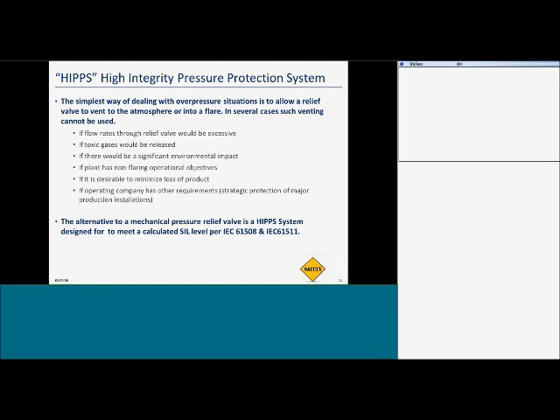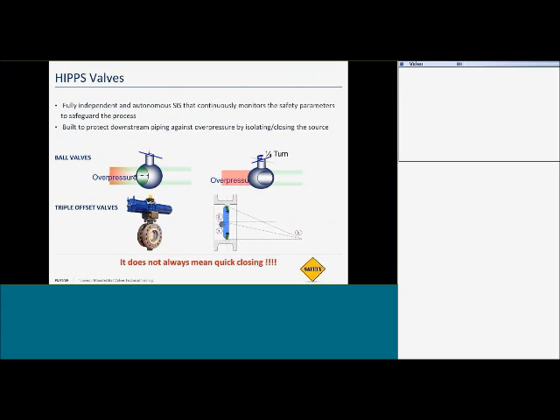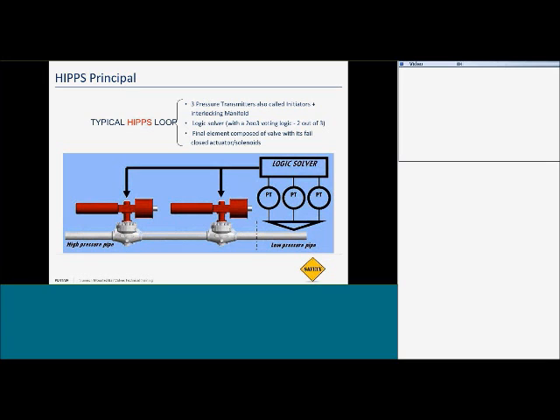We do see them all the time in offshore because of the high pressure processes that they have in offshore. And as I said, ball valves are the most common valve solution, although triple offset valves are acceptable in most applications. This is a typical HIPPS loop. We already took a look at one example of this where you've got your pressure transmitters, your logic solver, and then your final element composed of fail closed valves.